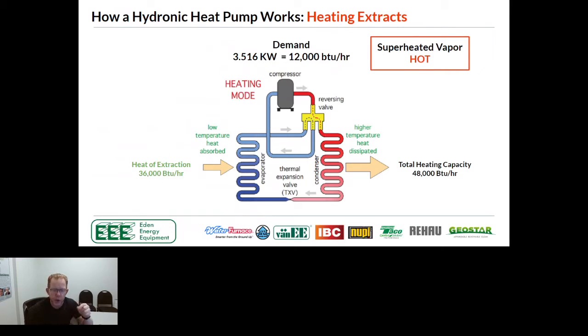The other thing to be aware of is that cold climate heat pumps are able to go to much, much lower air temperatures. Gone are the days where it's -2 and you can't run your heat pump. That's not the case. All of the units that we've looked at, you can see the performance tables, even at -12, they're still, if it's a 40,000 BTU unit, sitting at around 36,000 BTU. So it's not like you're losing the entire capacity of the unit. You do want to pay attention to that, though, that there is that drop off.